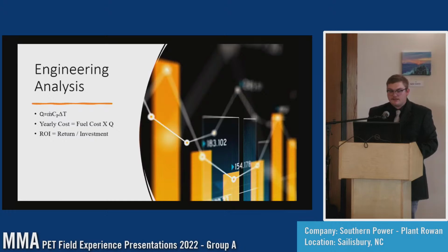So I had to find multiple things for my calculations. I had to find the mass flow rate of the fuel, the specific heat capacity of the fuel, and the temperature rise. The temperature rise I got from the Piedmont engineer, and the specific heat I got from a fuel report, and the mass flow I got from the OIS. And I used these to calculate the heat capacity of the heater. And with that, I could calculate the yearly cost with the fuel cost. And with the yearly cost, I could do the ROI equation, which is return over investment.